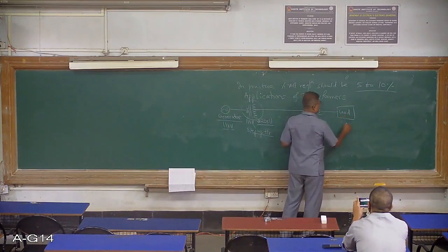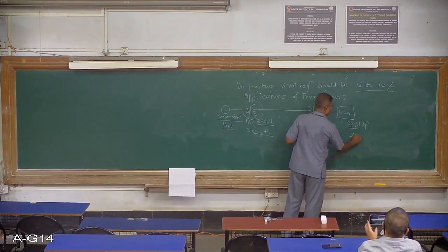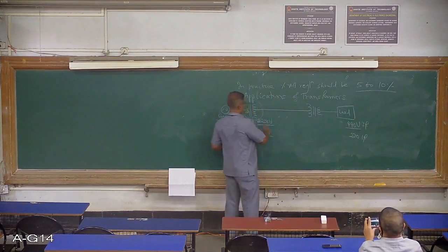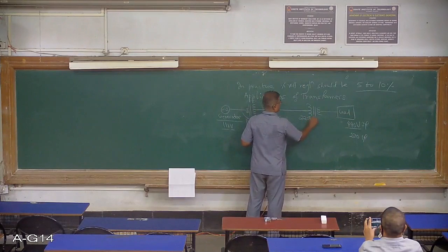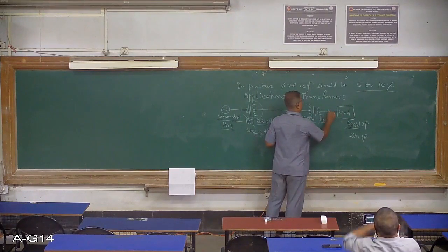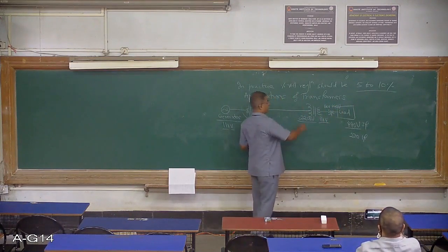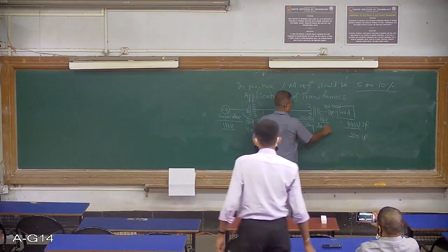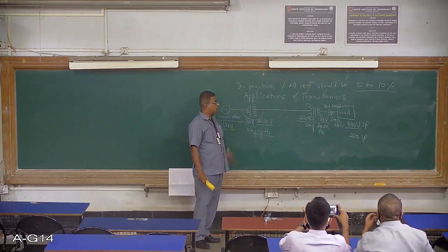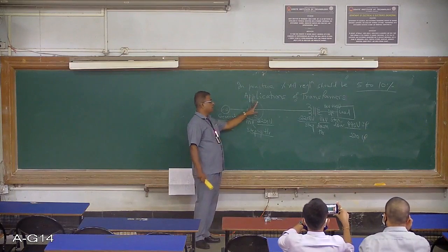In the load, the level of the voltage has to be reduced to the extent of 440 volts three phase or 230 volt single phase. So in the rear end of the power system, at the domestic level, the voltage has to be reduced. So the 220 kilovolt voltage has to be reduced. First it is reduced to 11 kilovolt in the first stage. Then later, once again, one more transformer we have to use to further reduce the voltage from 11 kilovolt to 440 volt. Okay. So in the rear stage, we need step down transformers. So prominently, we need the transformers in the power systems, which are the integral parts of any power system. So that is the primary application of the transformers.